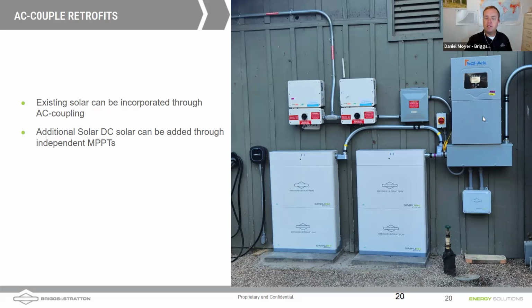and we're feeding into this Sol-Ark 15K onto the gen input. Down below, these are our 6.6 stacking batteries. So we have two stacks of two, and each one of these is coming in. We have pre-punched knockouts for 2-inch conduit, bringing that on here, and we're feeding that DC right into the Sol-Ark 15K, which has dual battery inputs as well.